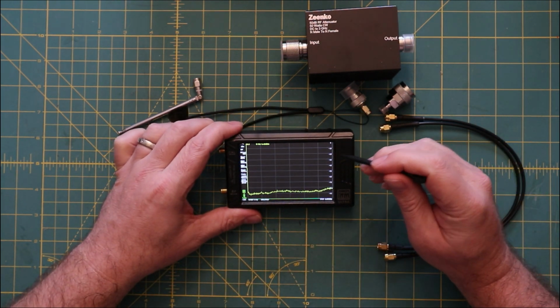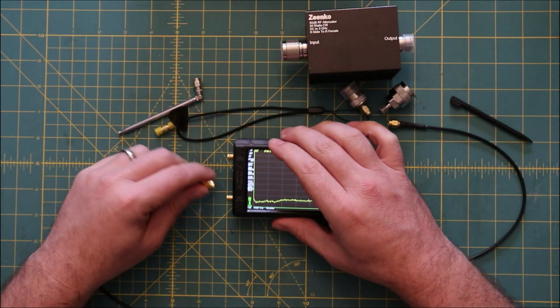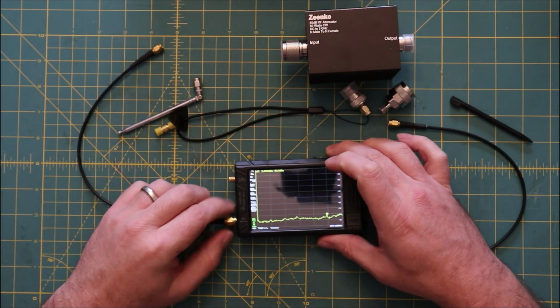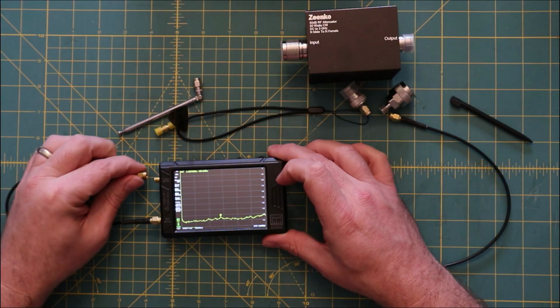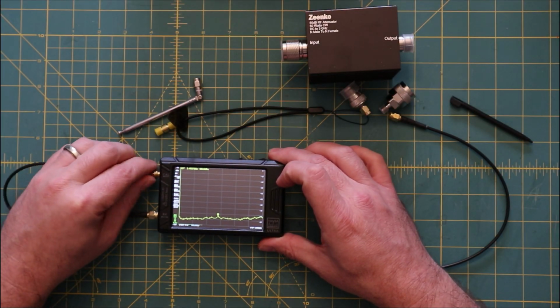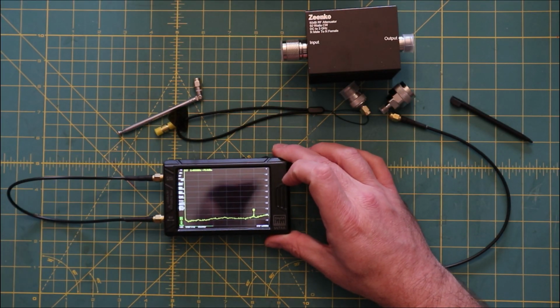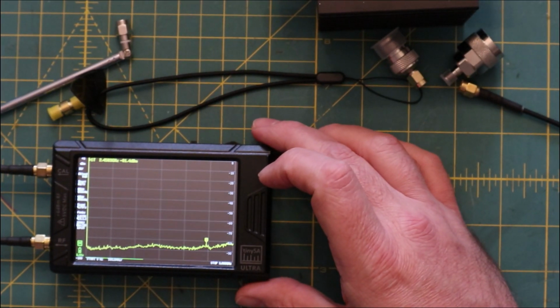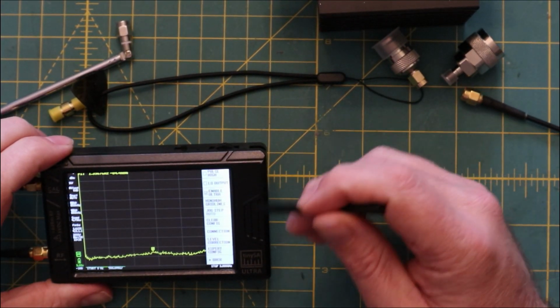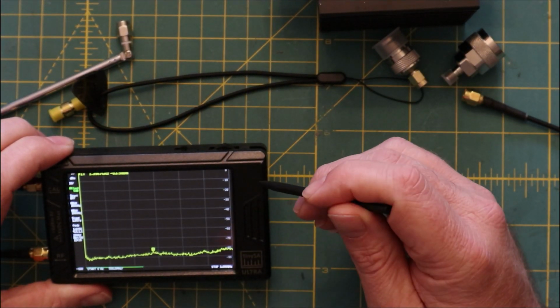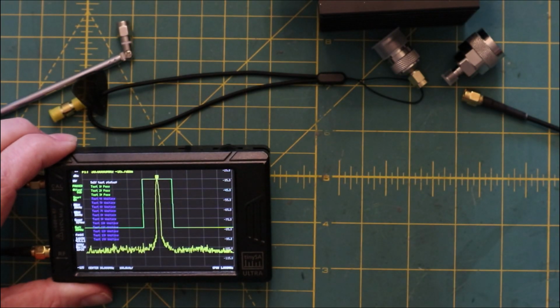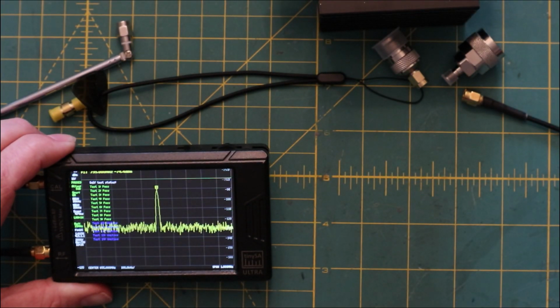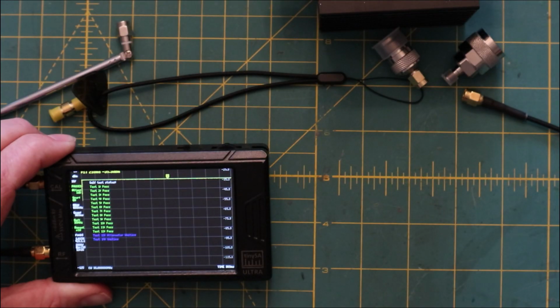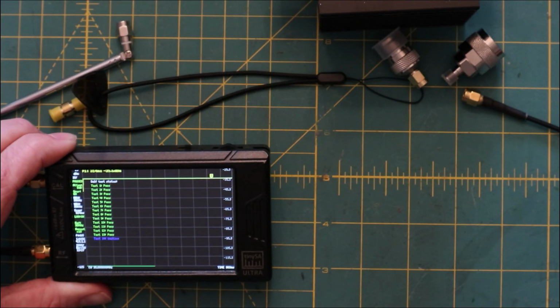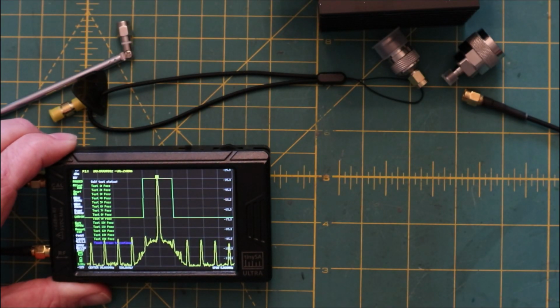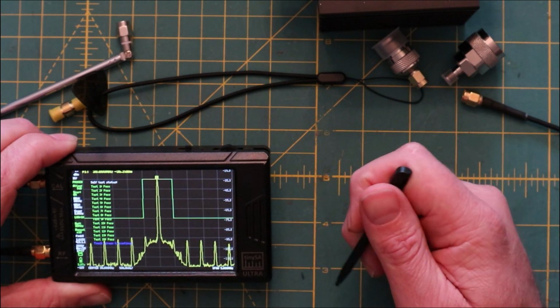Next, we'll perform a series of self-tests and calibrate it. To do that, we connect the calibration port on top to the RF input on the bottom, then select Config and then Self-Test. It'll go through a series of screens performing the self-test, and as it runs, all these lines slowly turn green as each test completes successfully.